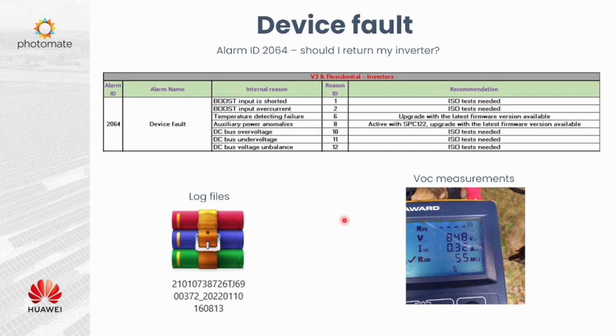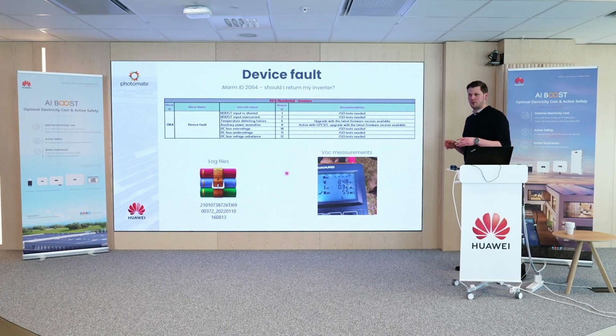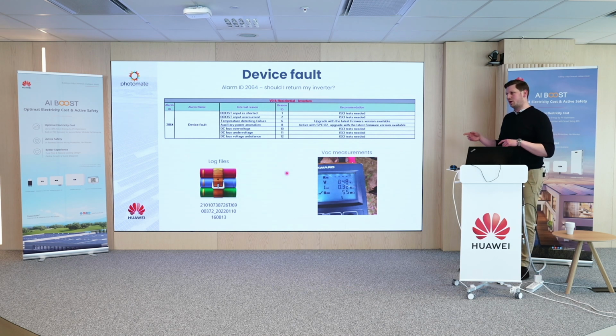The Huawei warranty process will require you to make at least insulation measurements before sending the faulty inverter back. So download the log files, make the insulation measurement on the PV side. Sometimes you may even be asked to make a photo of the VOC, the open circuit voltage. If you collect those materials, I can assure you, you'll have a positive decision for replacement the same day. If you just remove the inverter before doing this, the whole warranty process will be very complicated after and will take some time.